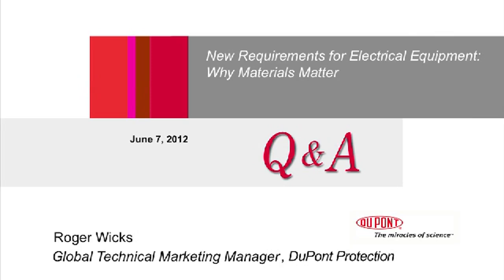Another question from the audience asks, is it mean then in high voltage transformer 418 is better than 410? I think what it meant is, is 418 better than 410 in high voltage transformers? The 418 is specifically designed for applications with higher volts per mil stresses, and any material like 418 that contains mica is much more capable of withstanding partial discharge. And so yes, 418 will operate better under very high voltage conditions.